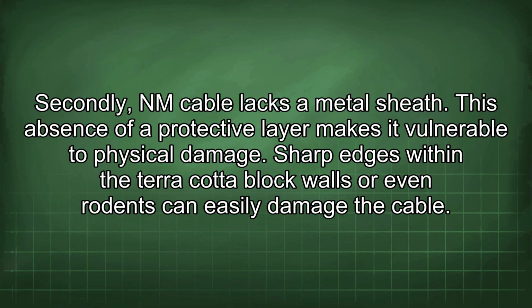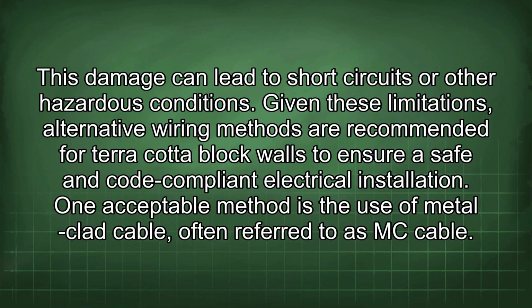Secondly, NM cable lacks a metal sheath. This absence of a protective layer makes it vulnerable to physical damage. Sharp edges within the terracotta block walls or even rodents can easily damage the cable. This damage can lead to short circuits or other hazardous conditions. Given these limitations, alternative wiring methods are recommended for terracotta block walls to ensure a safe and code-compliant electrical installation.